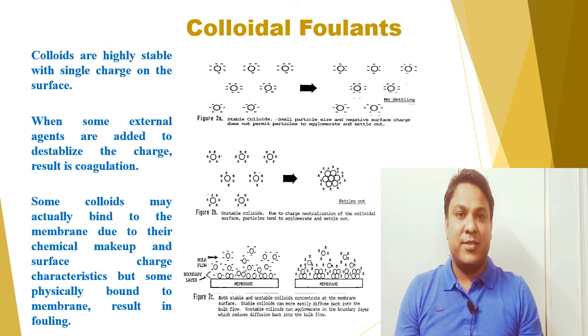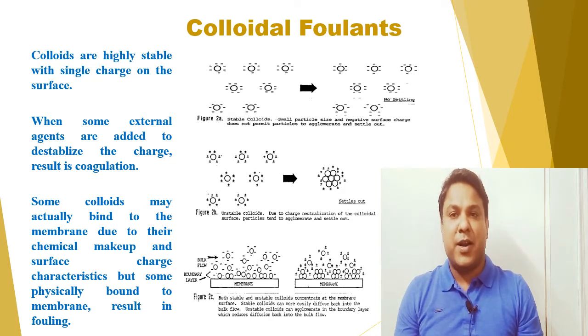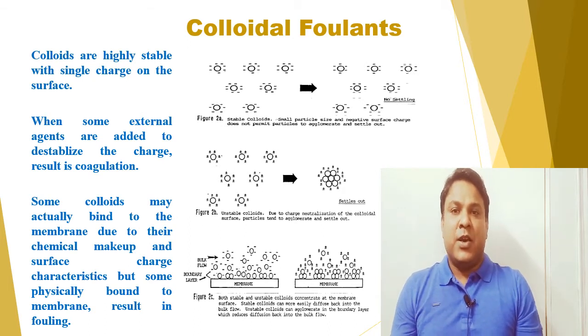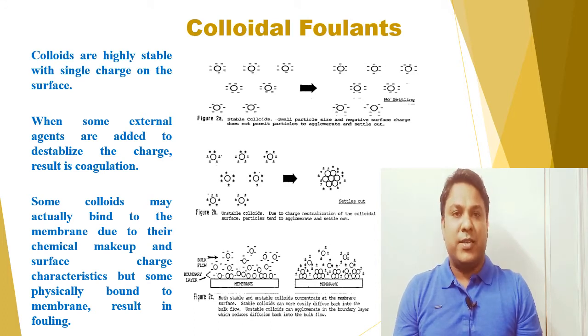Colloidal foulants. Here colloids are inorganic or mixed inorganic-organic based particles that are suspended in water and do not settle out due to gravity. Colloidal matter typically contains one or more of the following major components: iron, aluminum, silica, sulfur, or organic matter.